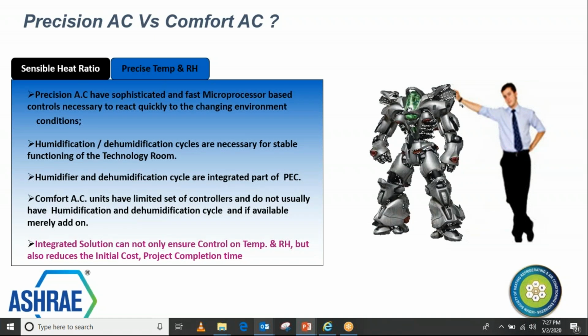Although the control could vary on temperature from plus minus 1, or even plus minus 0.5, to even plus minus 2 or plus minus 3 at some level, most cases go around 0.5 to plus minus 1 or plus minus 2 maximum on the temperature side. And on the humidity side, it goes from plus minus 3% to plus minus 5%, and in very few cases plus minus 10%. So this is really important to know, that is why temperature and humidity control is important.